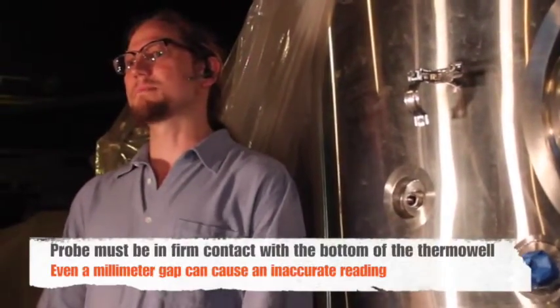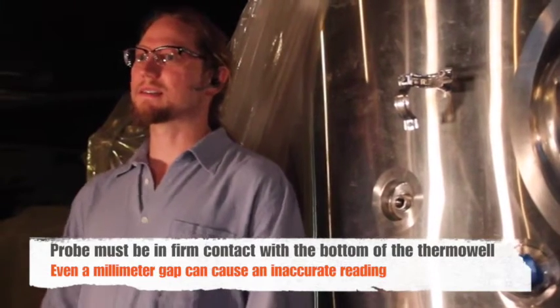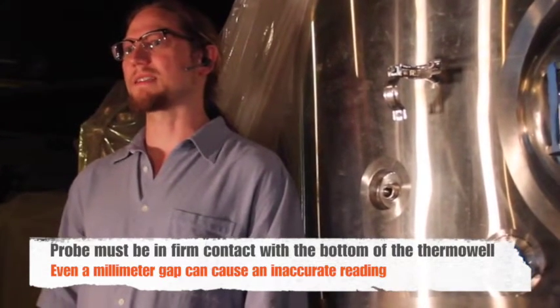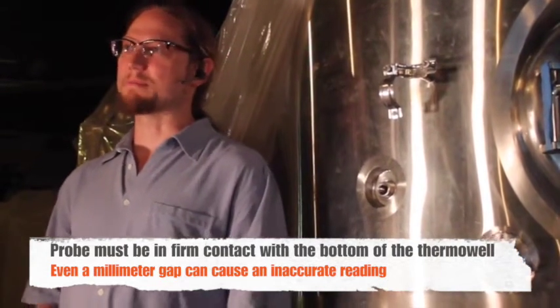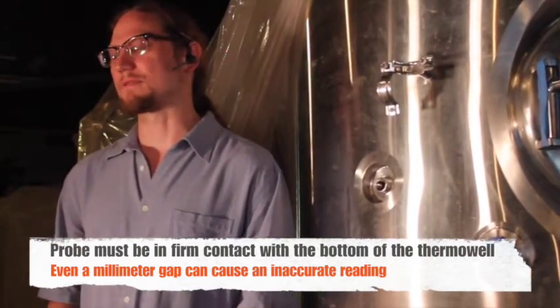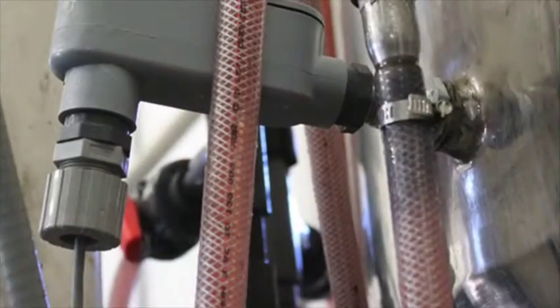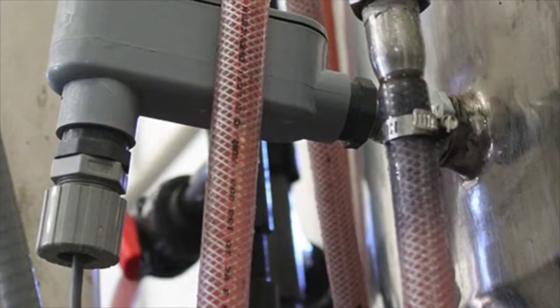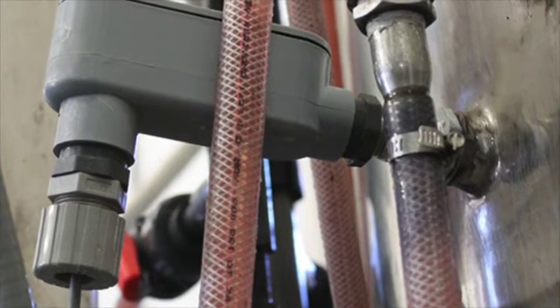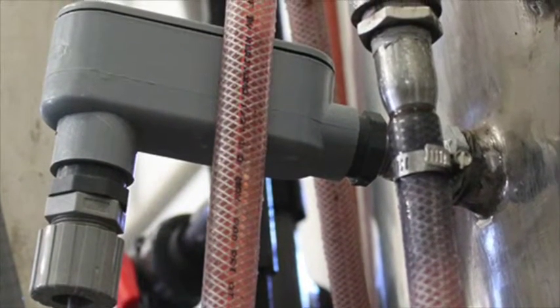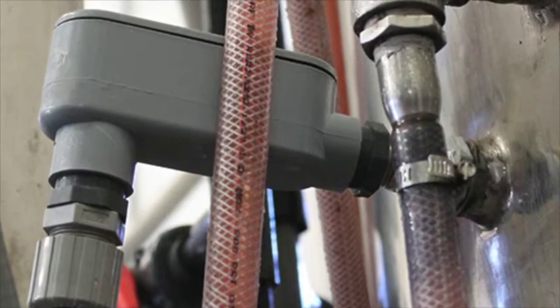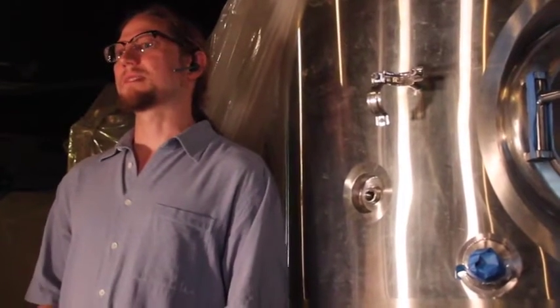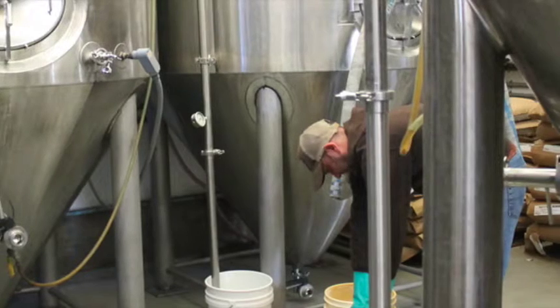In order to accurately measure the temperature inside of the tank, the temperature probe must be in firm contact with the bottom of the thermowell. A gap of even a millimeter can cause an inaccurate reading. Thermowells generally come in standard lengths, so in theory, if one uses a standard length probe with a standard length thermowell, everything will work. But that's theory. In the real world, this is often not the case.